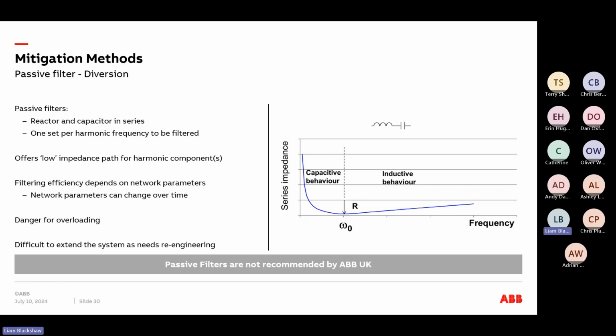Then we have one set per harmonic frequency that's filtered, but also offers a low impedance path for harmonic components. And the key thing is that the filtering efficiency depends on the network parameters. So, and this is the key thing about that, a lot of engineering is involved, or a certain level of engineering is involved, to get the right passive filter set up. And if those network parameters change over time, which they can do, there's a danger there where that passive filter can overload.